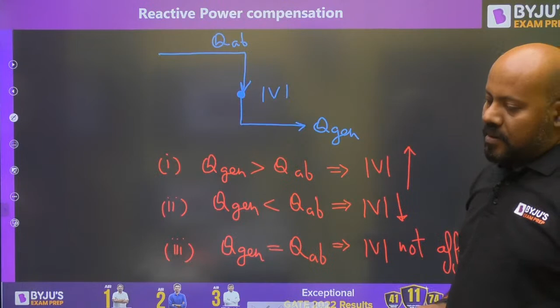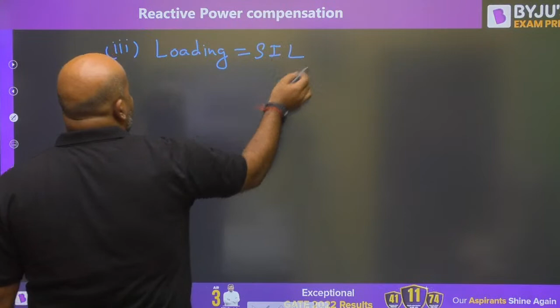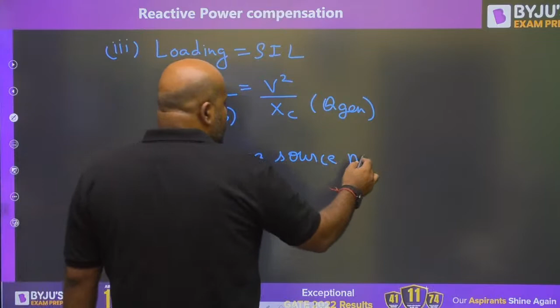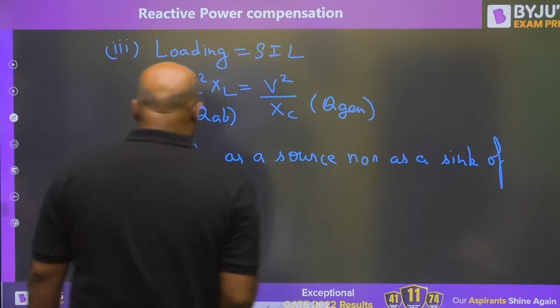Is it clear? So by using this logic, you can understand for the three conditions how your transmission line is going to behave. The third part is when your loading is equal to surge impedance loading. In this condition, the reactive power absorbed is equal to the reactive power generated. This is reactive power absorbed and this is reactive power generated. So we say that your line acts neither as a source nor as a sink of lagging reactive power.